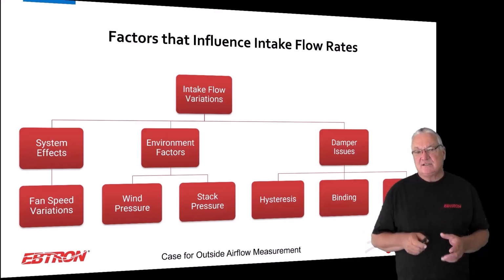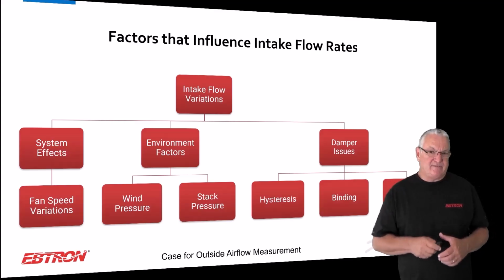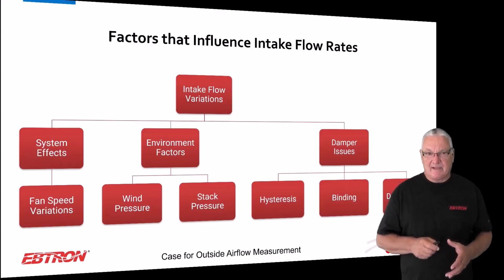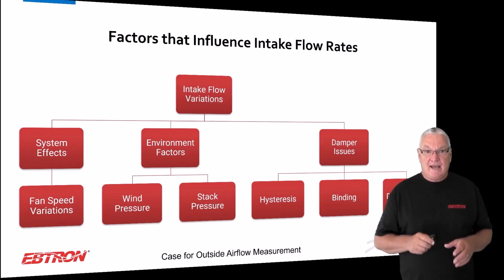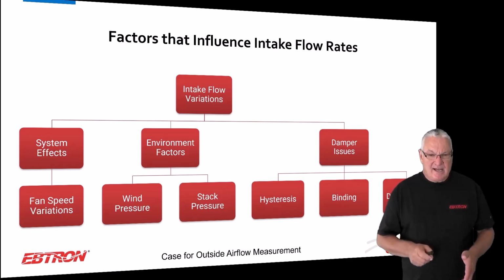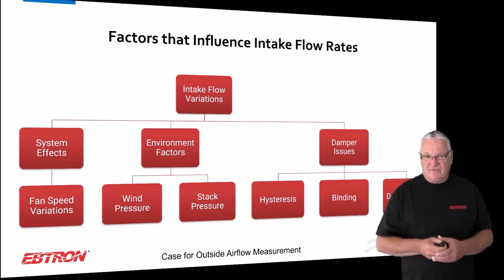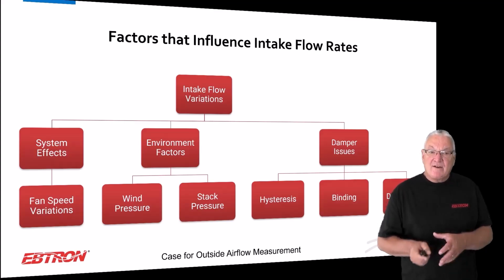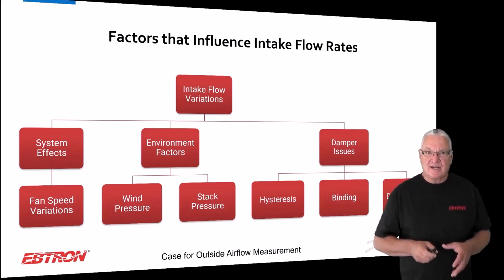I don't necessarily want you to be where it's like, oh yeah, I have to put a flow meter directly in the outside air path, but I do want you to be at, I better do something about this because I can't rely on damper position or multiple damper positions. I have to figure out the outdoor airflow rate coming into the system, whatever system it is. That's where I want you to be now.